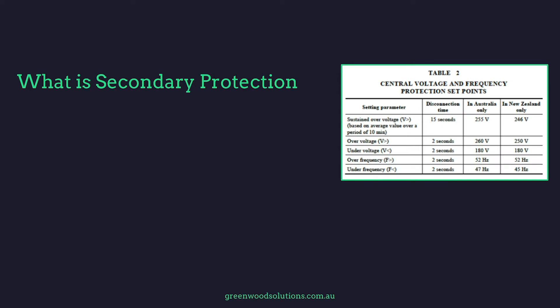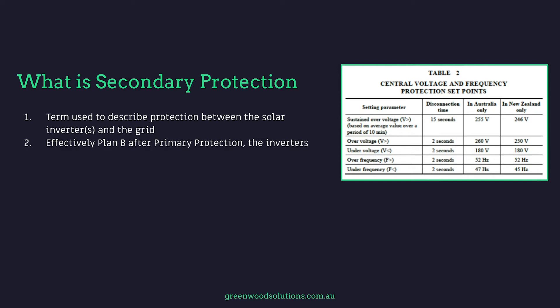What is secondary protection? It's a term used to describe protection between the solar inverters and the grid effectively. So it's plan B after the primary protection of the inverters. It consists of various components inside an enclosure. Things such as over voltage, under voltage, over frequency and under frequency can be set. And it's designed to protect the grid.